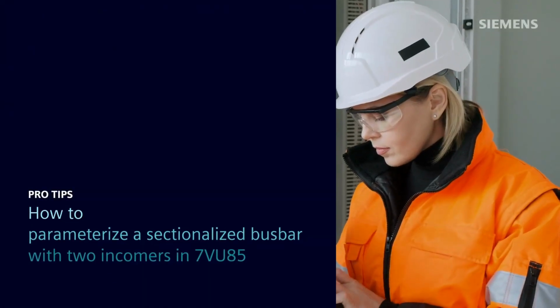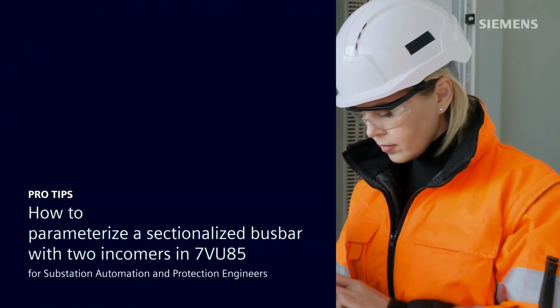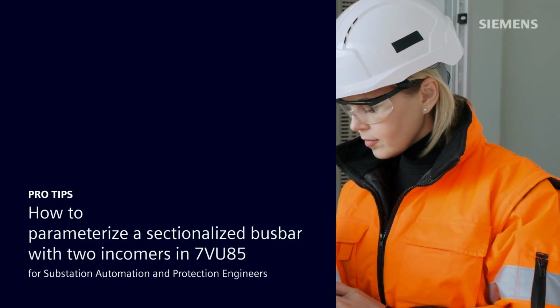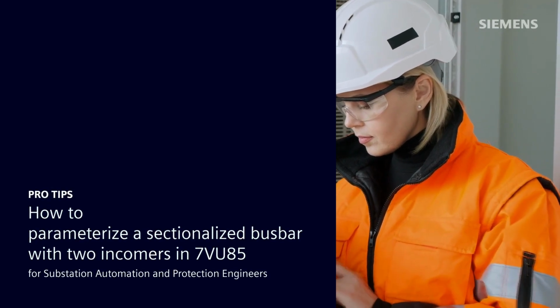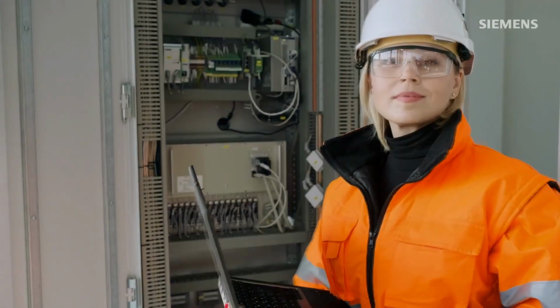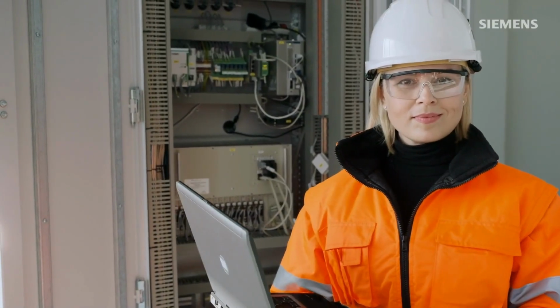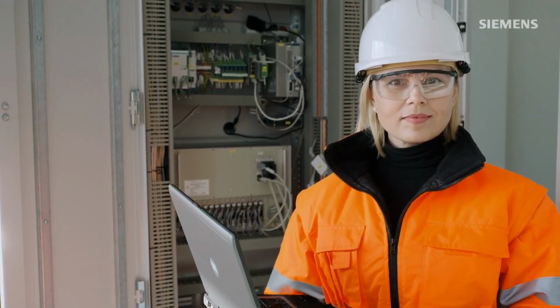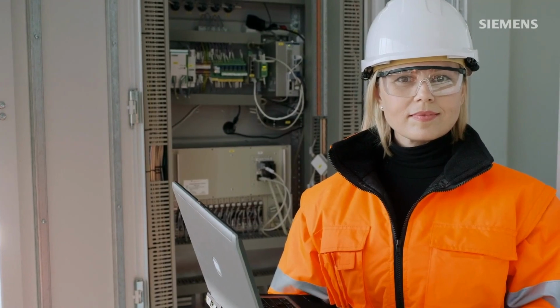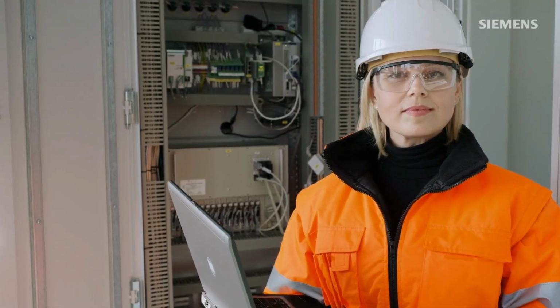The sectionalized busbar with 2 incomers is a common application in industrial plants. The SIPROTEC 7VU85 high-speed busbar transfer device provides a template for this application. Today, I will show you how to configure this application template by using DIGSI 5 software.